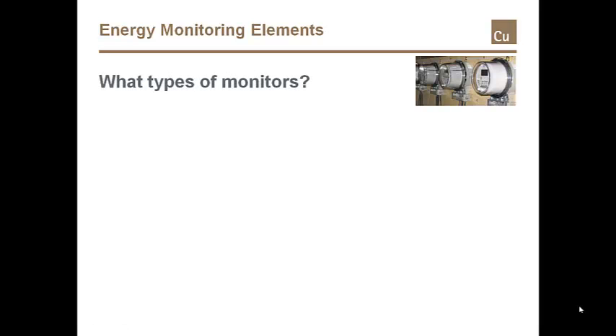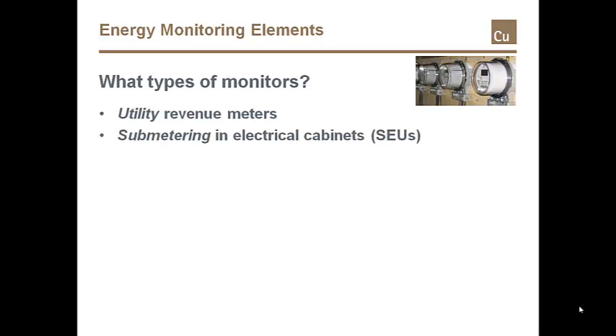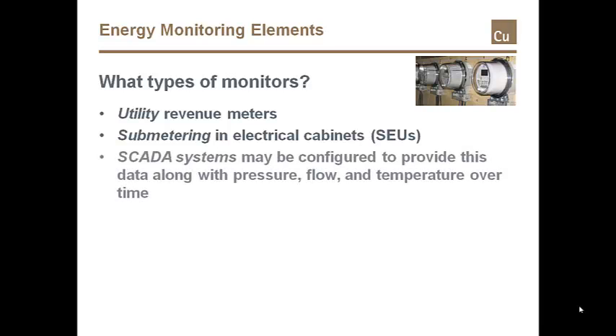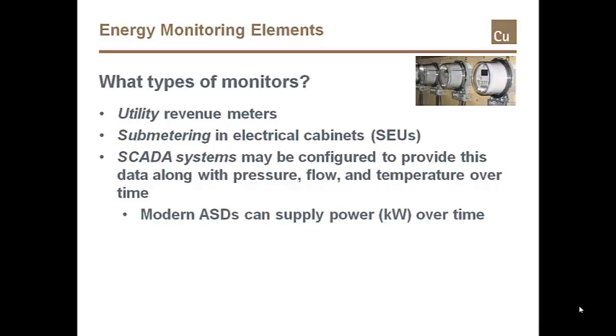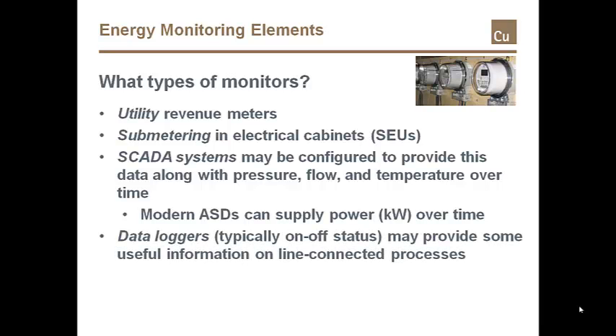What types of monitors may supply the required information? Utility revenue meters at minimum. Sub-metering is possible in electrical cabinets supplying SEUs, that is, significant energy uses. SCADA systems may be configured to provide this and other data. Modern ASDs controlled by the SCADA system can supply power measured in kilowatts. Data loggers, typically on-off status devices, may provide useful information on the operation of line-connected processes.